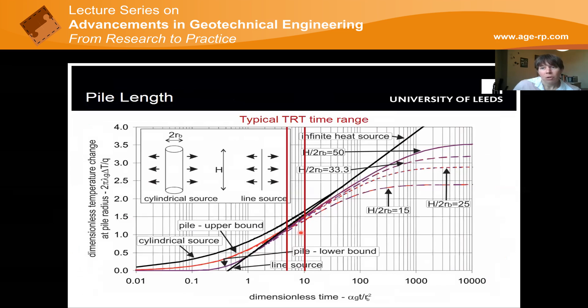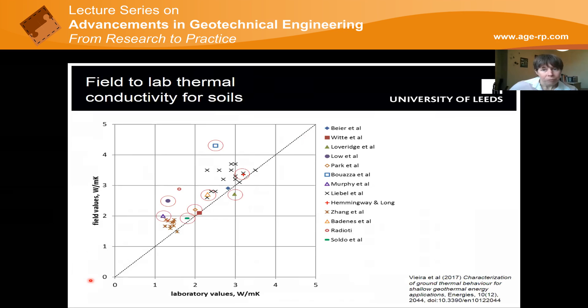And I can illustrate that by showing you some comparisons of field data against laboratory data for thermal response tests. Some of these are in boreholes and some of them are in piles. These ones in red circle are in piles. You can see there's a systematic overestimation in the field compared to laboratory testing when you test energy piles in the field. So you really have to be quite careful with this technique. I would say proceed with caution for thermal testing of energy piles, especially with large diameters. And don't plan to do a test unless you have got a more sophisticated interpretation method.